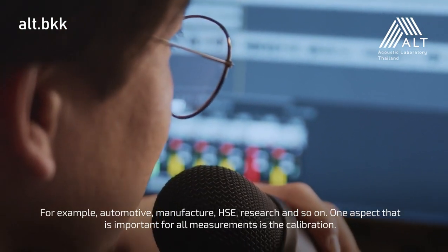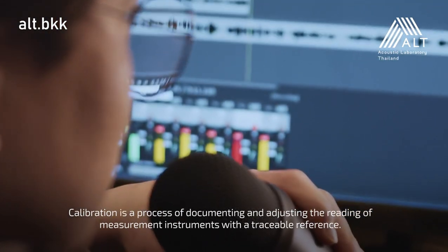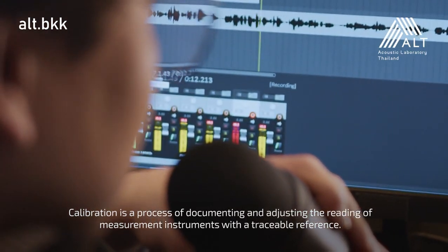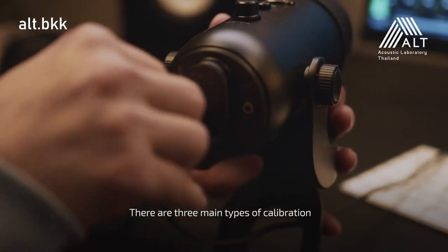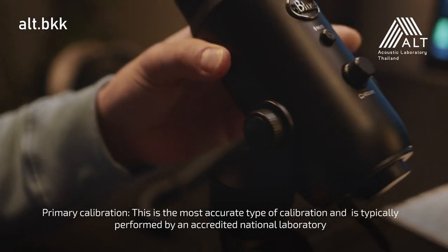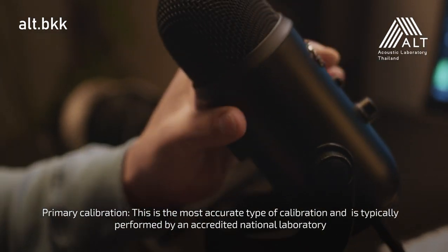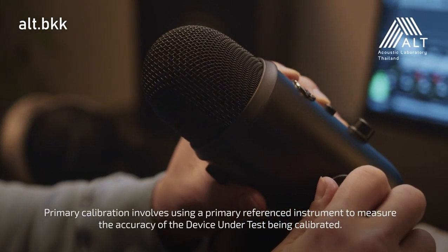One aspect that is important for all measurements is calibration. Calibration is a process of documenting and adjusting the reading of measurement instruments with a traceable reference. There are three main types of calibration. Primary calibration is the most accurate type and is typically performed by an accredited national laboratory.